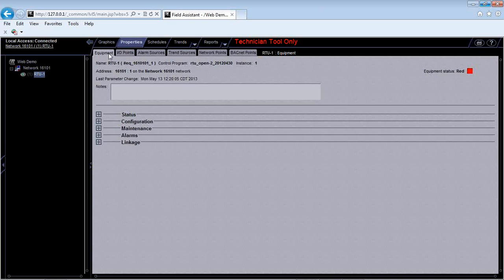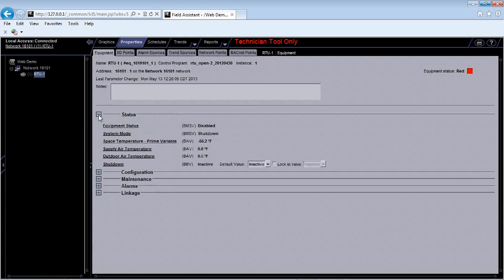Okay, so I have some drop downs here. I have a status drop down. If I look at it, it will tell me what my unit's doing currently. So right now my equipment status is disabled, it's not functioning, I'm in shutdown mode, and you can see I have a space temperature value reading of minus 56.2. That is a crazy value. I'm not reading 56.2 degrees Fahrenheit. That means I do not have a sensor wired in properly, okay? So I also don't have a supply temperature sensor, I don't have an outdoor air temperature sensor, okay?